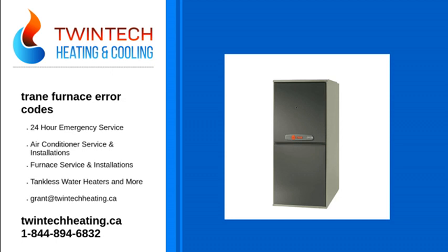Code flashing slow. Result: normal, no call for heat. Fix: this is only an issue if you have raised your thermostat and your furnace doesn't respond. Code flashing fast. Result: normal, call for heat. Fix: only beware of this if your furnace is continuously calling for heat and isn't responding to your thermostat.